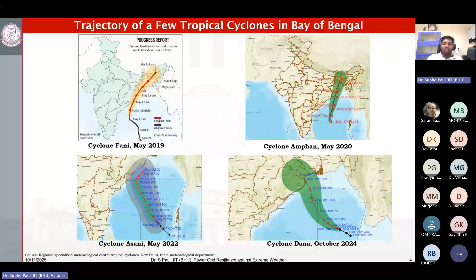That progression of the cyclones mainly causes the falling of electricity poles, as seen in the images of the damage caused by Fani in 2019. Coping with this situation is very difficult for any power grid because all the infrastructure is damaged. Mostly distribution poles, distribution lines, outdoor small substations and small pole-mounted transformers are the most vulnerable equipment exposed to these extreme weather events.